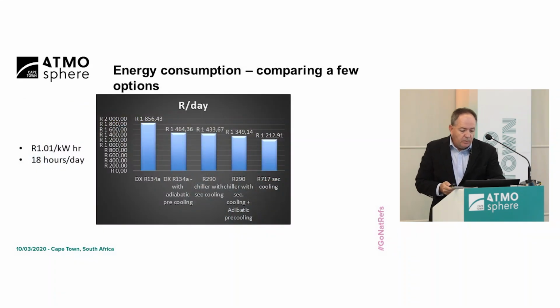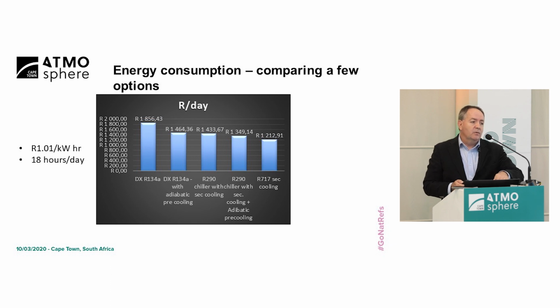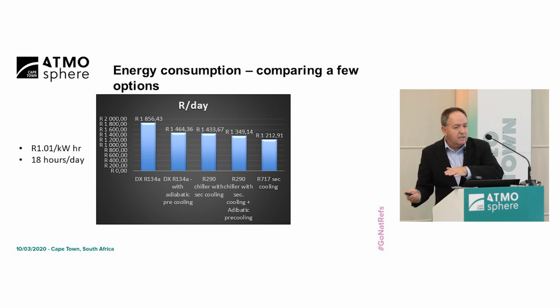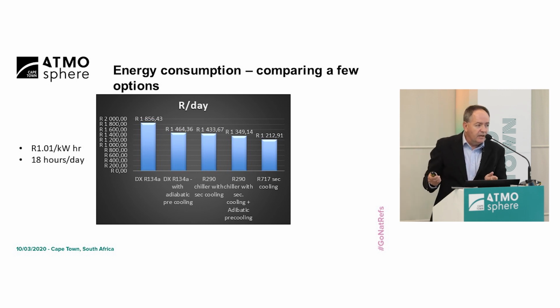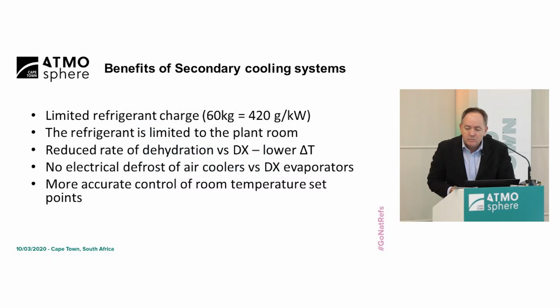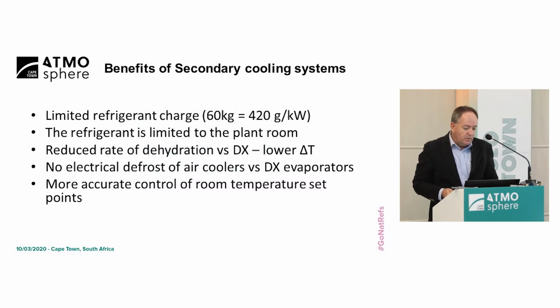I think what you want to see briefly, just as an energy review, is that we estimated 1,200 rands per day for the ammonia system, and the other extreme was an R134a direct expansion system. What we estimated and what they actually ended up using was fairly accurate, but they had operational factors like working on a Saturday that were difficult to factor in. So 420 grams per kilowatt hour. Refrigerant was limited to the plant room, and dehydration was really a big issue to this client. And there's no electrical defrost. That's a significant saving in energy because your air coolers don't ice up. So very moderate icing, and more accurate control of the room temperature, especially if you have a high value product like that. Okay, that's it.